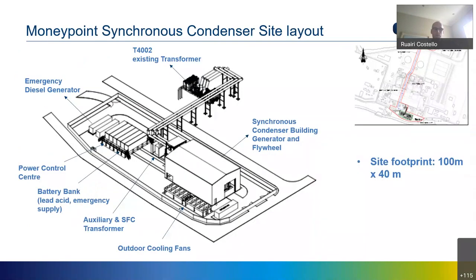So the site layout, if we start down in the bottom right, you've got cooling fans, and you've got the main machine house, which has the synchronous condenser and the flywheel. Then you've got the IPB with the circuit breaker to the left of that. And then it takes a right-hand turn up into the existing Unit 2 coal unit. We've also got some power control centers which contain batteries, control equipment, etc. And we've an emergency diesel generator on site as backup. But it was important to us that we size the batteries fully to safely run down the unit on loss of power from the grid.